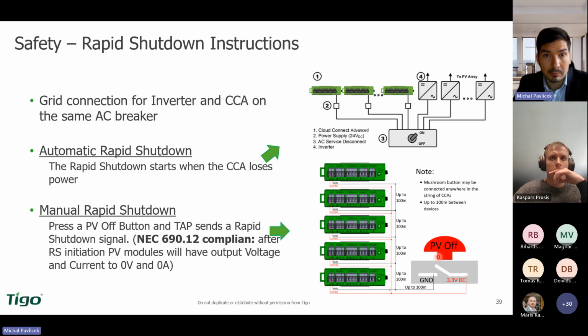And you also see it on the monitoring. When you touch it, you can also check on monitoring that it's really switched off, and you still see the monitoring. You are not losing monitoring. So you know whether this is under operation or under service. The same can be used also by maybe a person who is going to repair an air conditioning unit on the commercial roof. So he needs to maybe change the filters in the air conditioning system where there is a power plant. So he shouldn't enter until it's switched off. So by this single button you can switch off just the block around the air conditioning system. You can go clean the filters and go back, while the rest of the project continues in production.